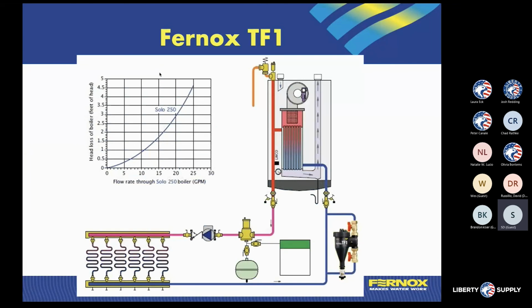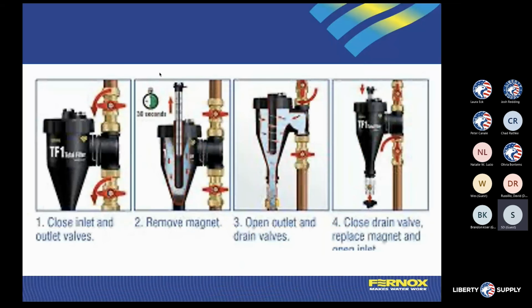So there's two different types of magnetic filters that you're going to be able to purchase. One is a bypass or maybe piped in a bypass. Most magnetic filters can be piped either in a bypass like we're looking at here, where we're not putting all of the return water through the system filter or that magnetic filter. They all use a cyclone style or a centrifugal style system.